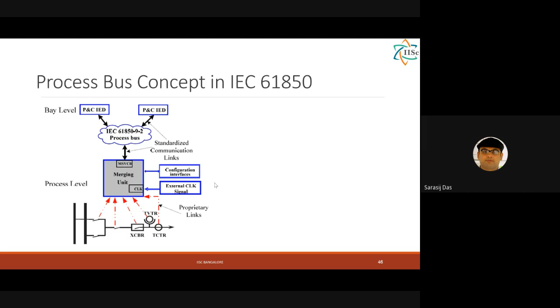So here you can see that from the merging unit, there is a process bus. Again, this bus is basically a communication network through which the digitized samples are sent to protection and control IEDs. Okay. Now, you can see that from the merging unit you have communication. To standardize this communication, IEC 61850 has defined three types of messages. GOOSE is one message type, SMV, sampled values, is another message type, and MMS is another message type. So, what is GOOSE?